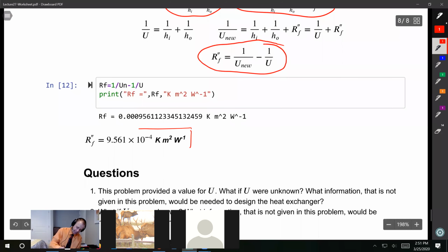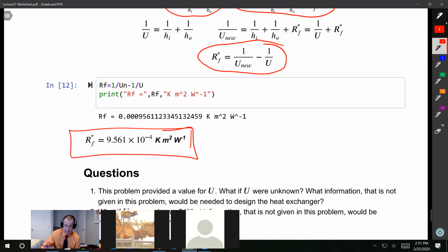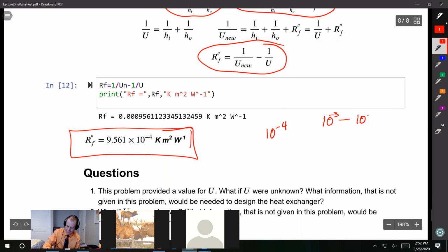I want to end with this, it's pretty significant. What is the value? You don't need to say it exactly, but it's like 10 to the minus 4. Typical fouling factors range from 10 to the minus 3 to 10 to the minus 5. If you go to 0, that would assume no fouling. This is very high.